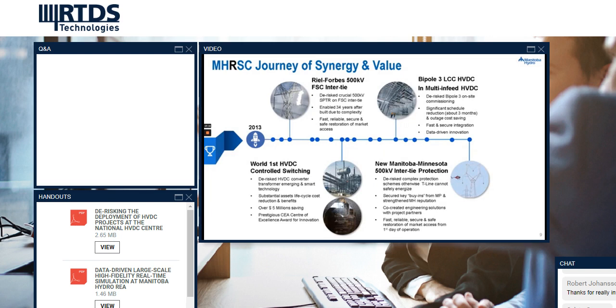This line is designed with 60% series compensation. Initially, there was a legitimate concern of high circuit breaker transient recovery voltage, TRV, due to the potential delayed clearing, given the presence of a very, very high degree of series compensation, which ultimately may give rise to missing current zero crossings.